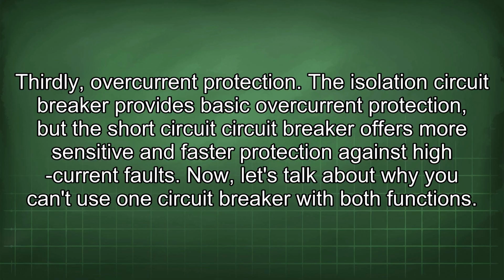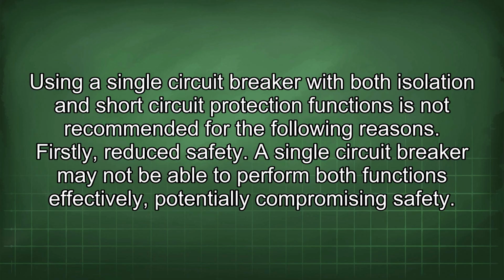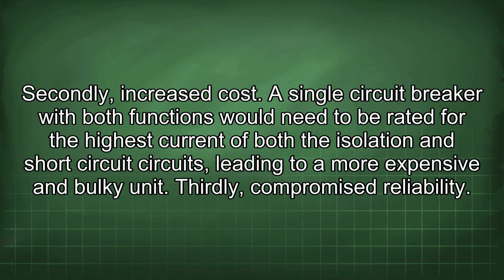Now let's talk about why you can't use one circuit breaker with both functions. Using a single circuit breaker with both isolation and short circuit protection functions is not recommended for the following reasons. Firstly, reduced safety. A single circuit breaker may not be able to perform both functions effectively, potentially compromising safety. Secondly, increased cost. A single circuit breaker with both functions would need to be rated for the highest current of both the isolation and short circuit circuits, leading to a more expensive and bulky unit.